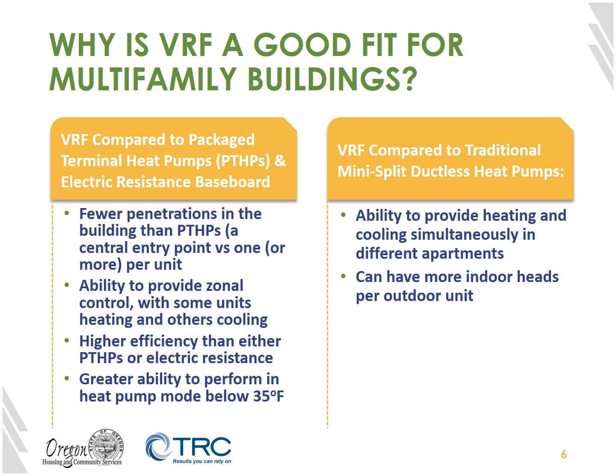If we had a traditional multi-split or mini-split system, we would have to do this by having a one-to-one system for every unit in the building. So that means if you have 48 units in your multifamily building, you would need to have 48 outdoor units on the roof compared to potentially one outdoor unit for the VRF system. So quite a bit of difference. They also can be a little bit more efficient than the base multi-split system.